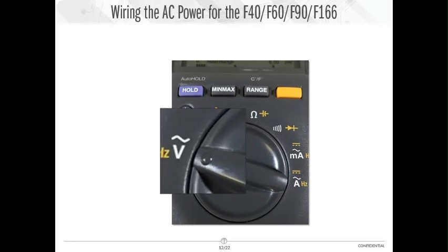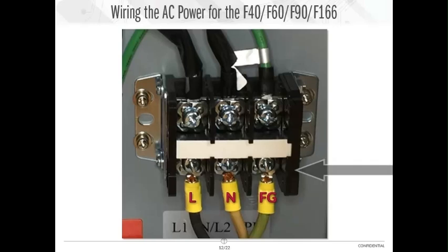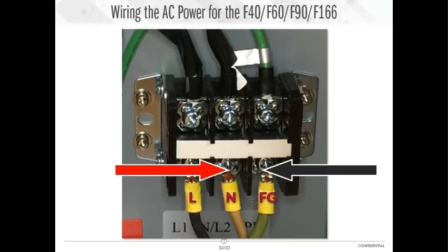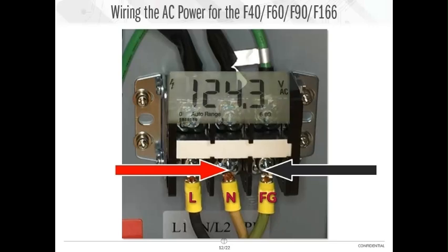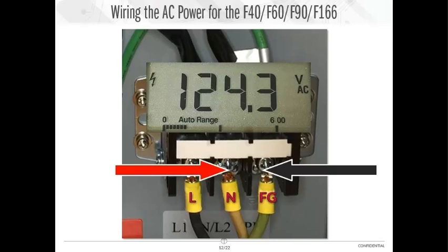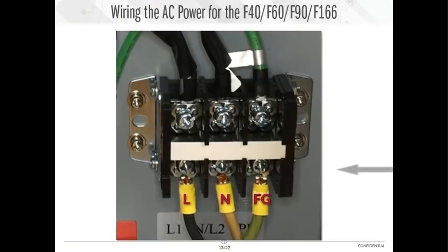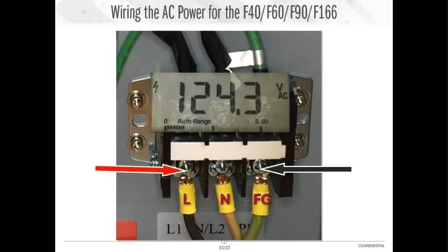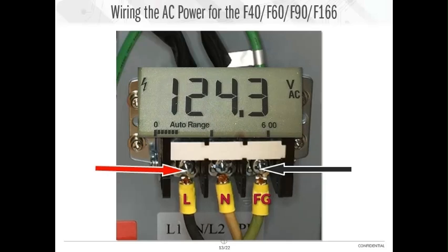Take the black probe of your meter and place it on the green wire terminal marked FG, and the red probe on the white wire, this is the terminal marked N, and measure the voltage. The voltage across these 2 points should be about 120 volts AC. Again, take the black probe of your meter and place this on the terminal marked FG. Place the red probe from your meter on the terminal marked L, this should be the black wire, and read the voltage on your meter. The voltage should be about 120 volts AC.